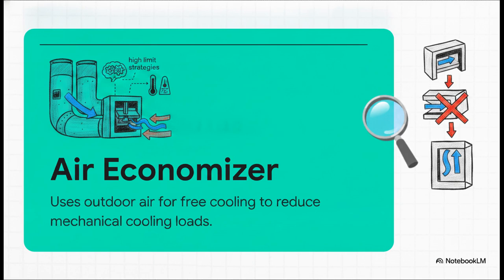An air economizer is a vital component of modern HVAC systems. Its entire job is to pull in outdoor air to cool a building for free, taking the load off those expensive mechanical systems. But the economizer can't just operate blindly, right? It needs what we call high-limit strategies. Think of these strategies as the brains of the operation. They're the logic controllers deciding when the outdoor air is actually good enough to bring inside, and when those dampers need to slam shut to keep the bad air out.